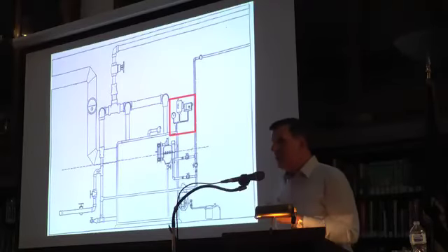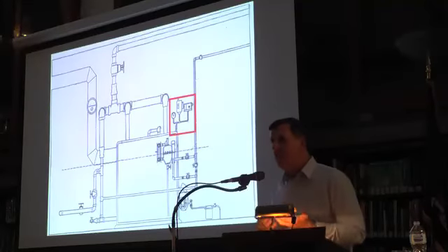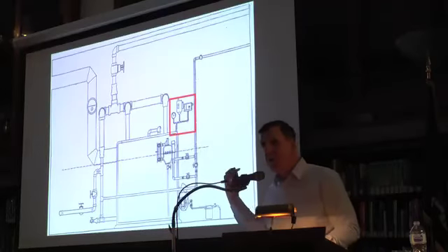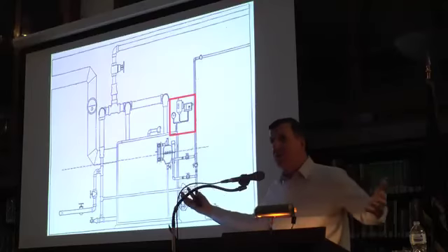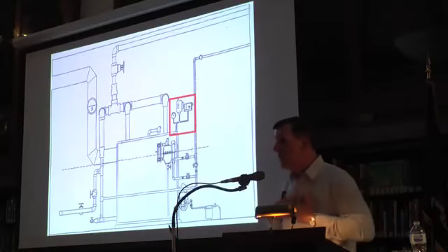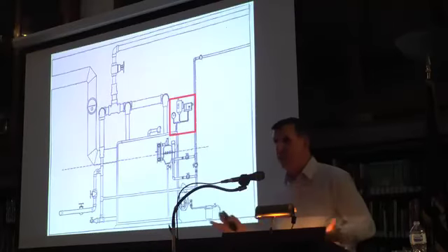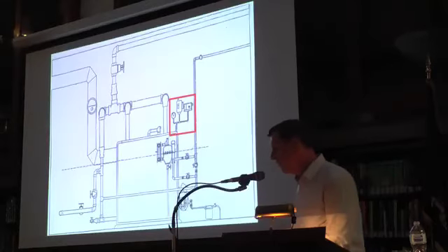Right? So, because what happens too is, I always tell people to work on these things, do not close the boiler room door if you're working on a steam boiler, because if that thing pops while you're working on it, the room is going to instantly fill with like 250-degree steam, displace all the air in the room, and suddenly you're breathing steam and there's no oxygen. So this will kill you in a moment. So you're going to keep the door open so it's got a place to go at least.